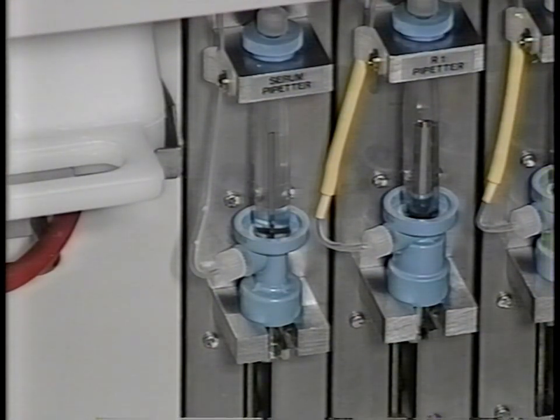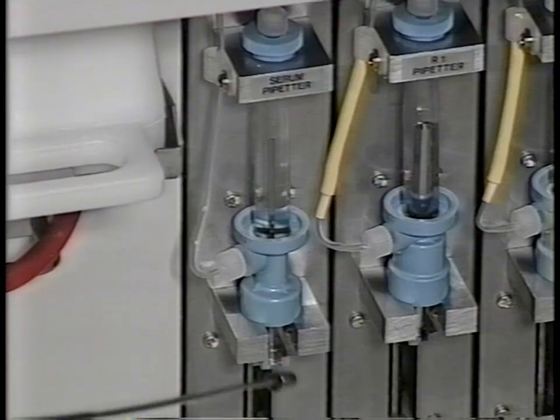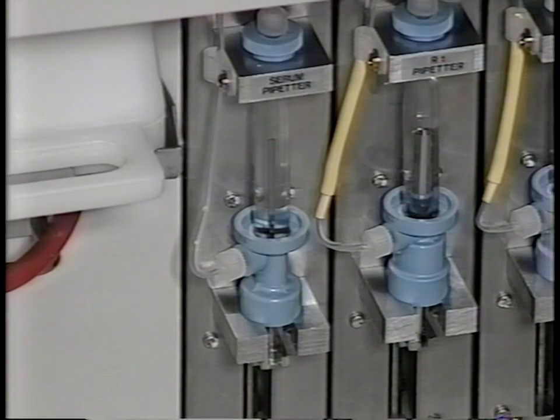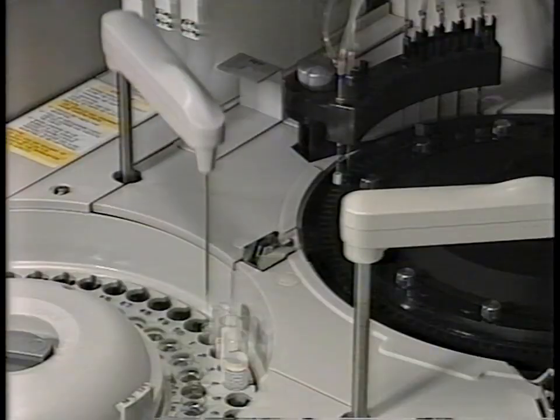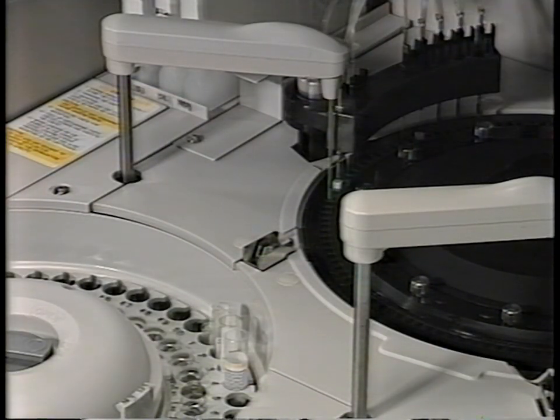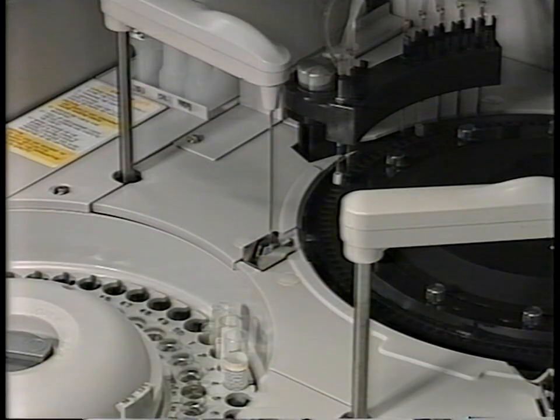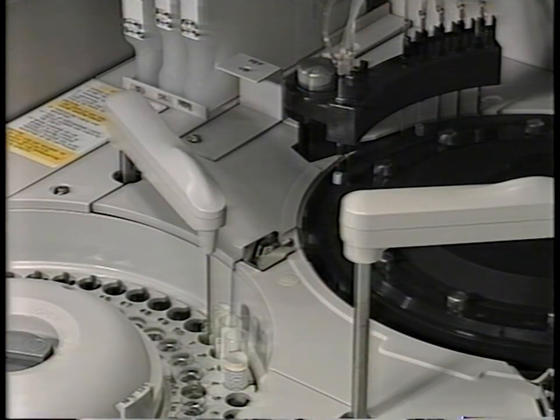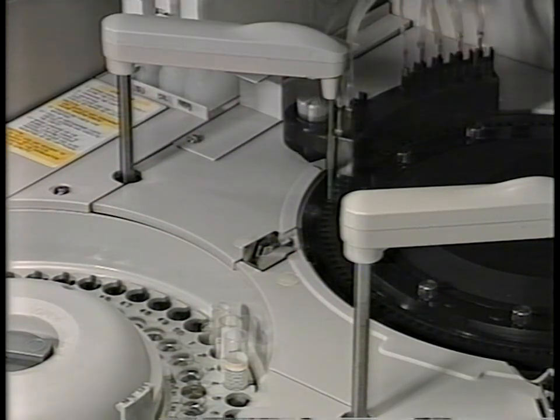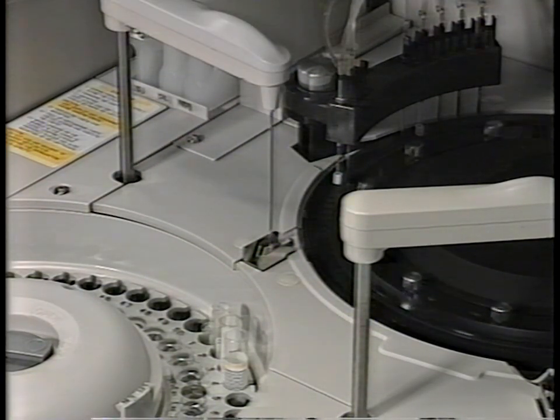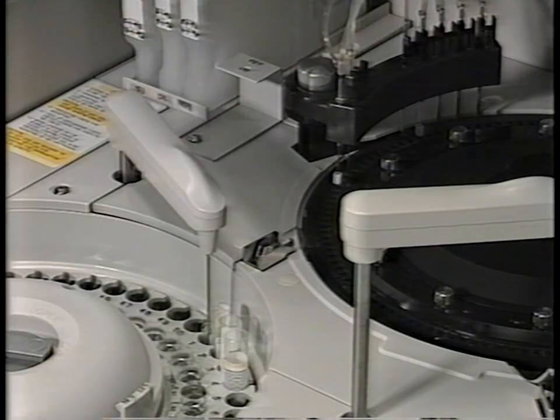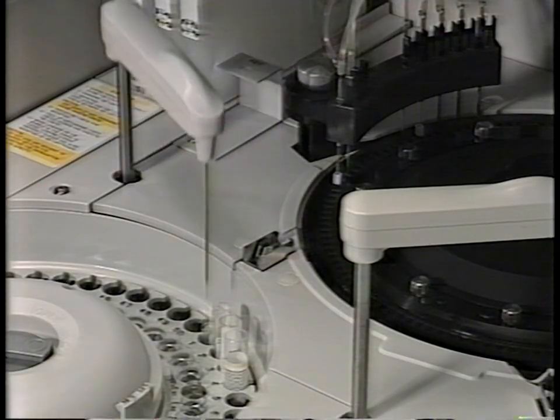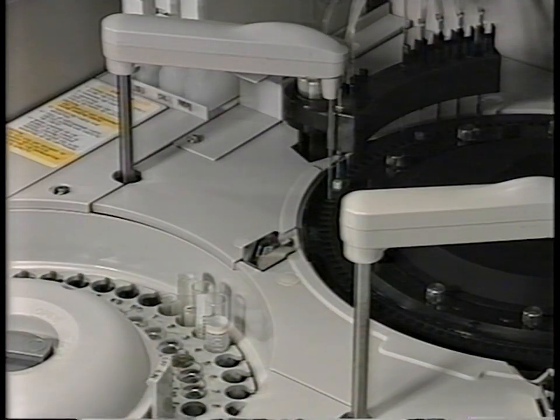Sample is pipetted by a positive displacement pipetter. Mounted in the cabinet below the analytical unit as we saw before, the pipetter and the tubing that connects it to the sample probe are filled with degassed, deionized water. As the probe dispenses aliquots of sample, it returns to the same sample until all tests selected for that sample have been pipetted. However, if a stat is requested, testing of the current sample is interrupted and the stat is processed. When all of the stat's tests have been pipetted, the system finishes pipetting tests for the interrupted sample.